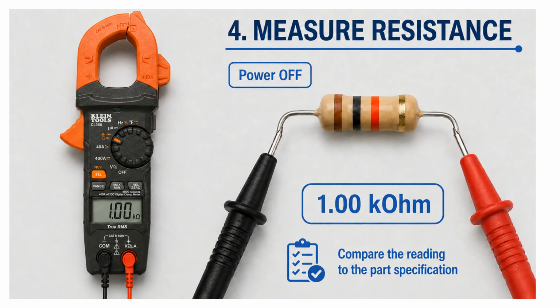The fourth use is measuring resistance. Resistance is how much something opposes the flow of electricity. It is measured in ohms. We may measure resistance when checking a resistor, heating element, sensor, coil, wire, or other disconnected part. Power must be turned off and disconnected before measuring resistance.